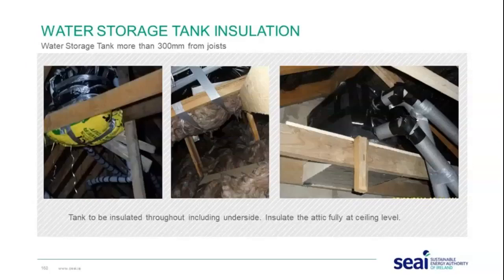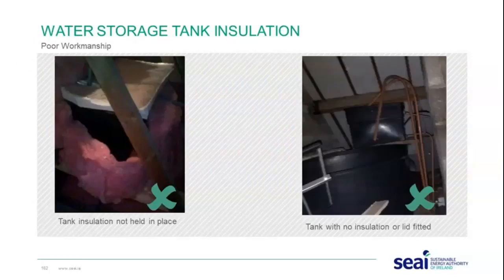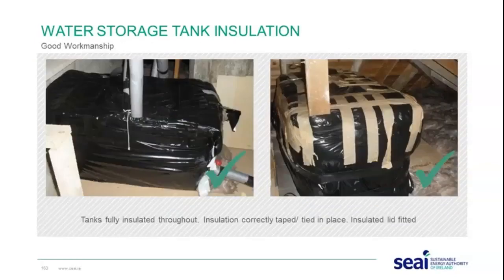For a water storage tank less than 300 millimetres from the ceiling: insulate to the side and lid, with no insulation fitted to the underside and no insulation between the joists under the tank — the quilt should be skirted up just around the underside of the tank. Where a supported storage tank is more than 300 millimetres from the joist, the tank is to be fully insulated including the underside.